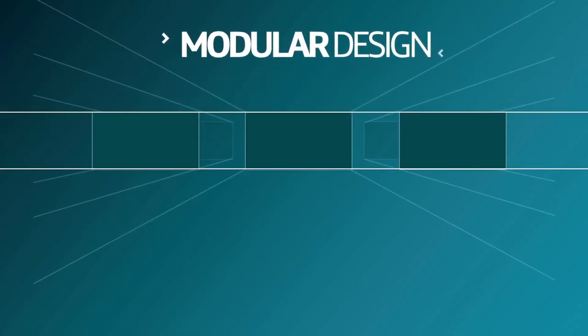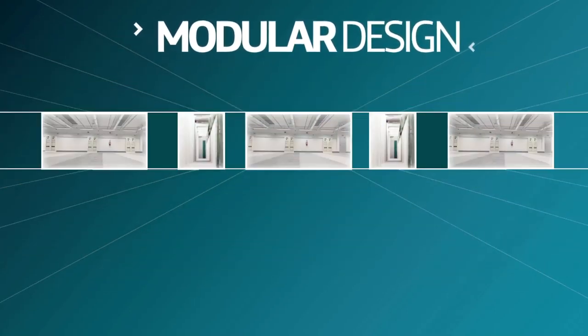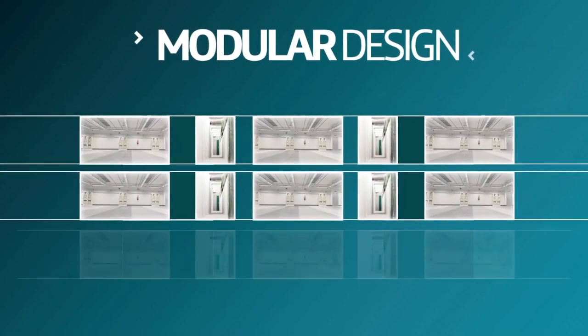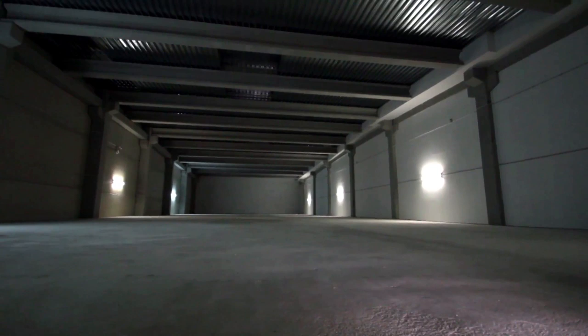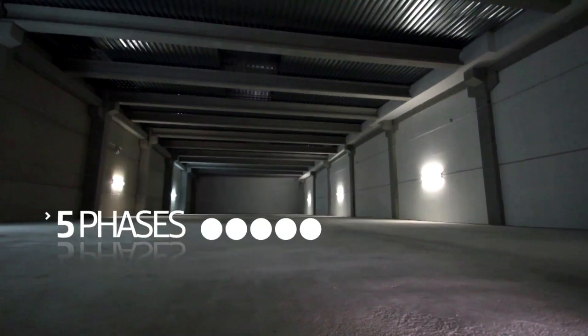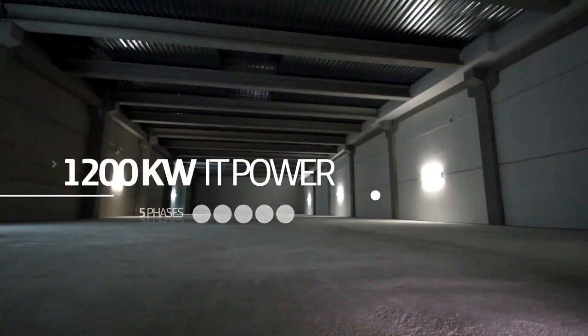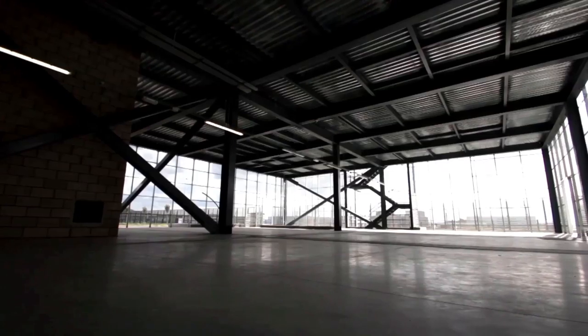We've used a special technique that enables us to roll out sections of the data center as they are needed, without compromising on functionality and security as it grows. The complex will unfold in five phases. The first phase will contain seven IT rooms and the others will have four IT rooms each, equipped with 1,200 kilowatts of IT power — the equivalent of 1.76 kilowatts per meter squared.